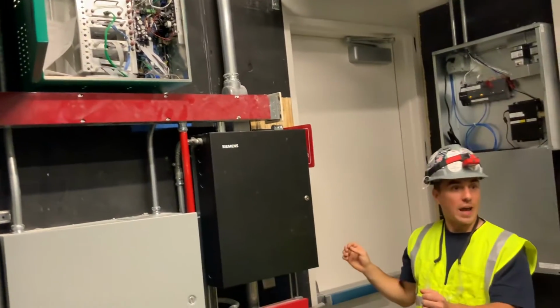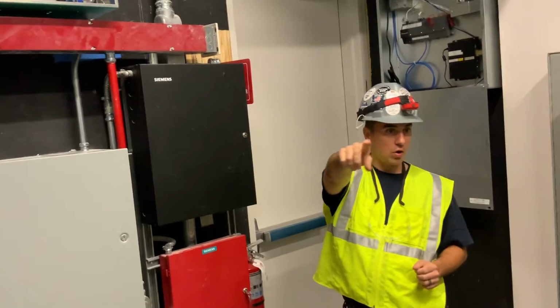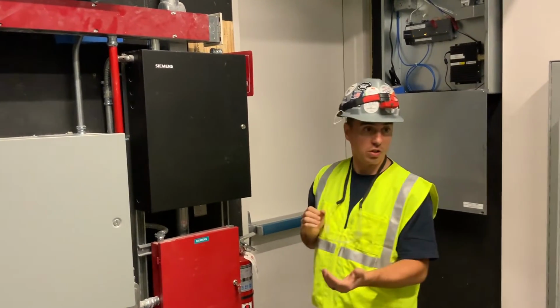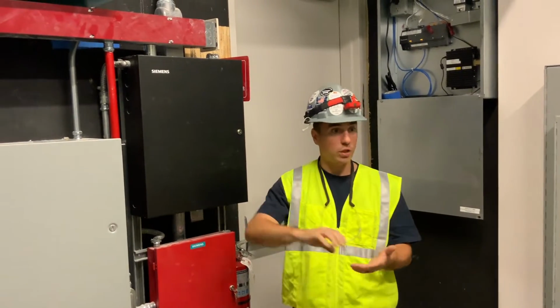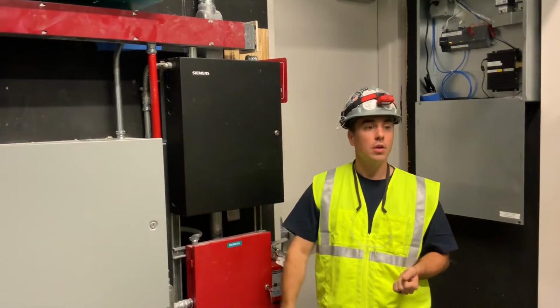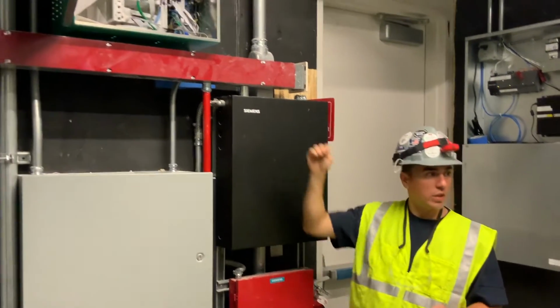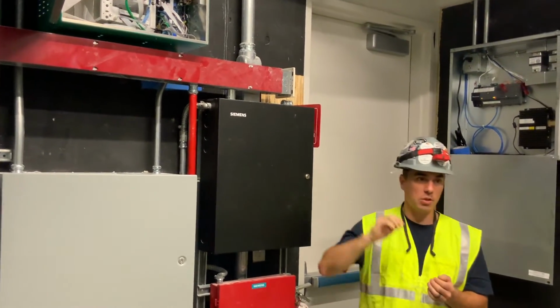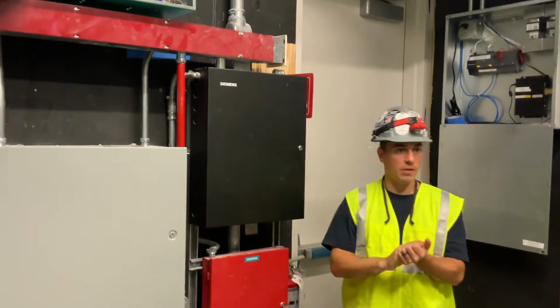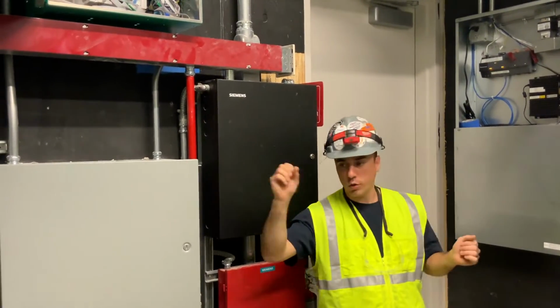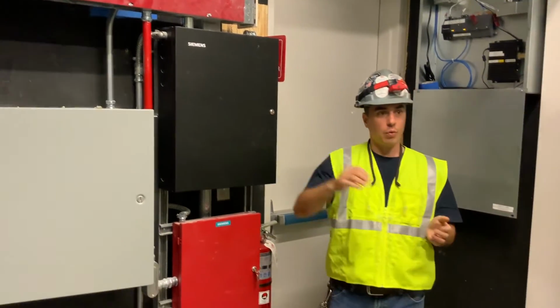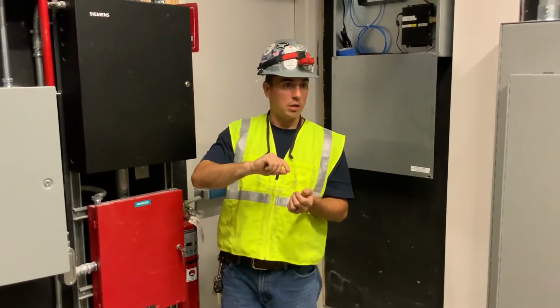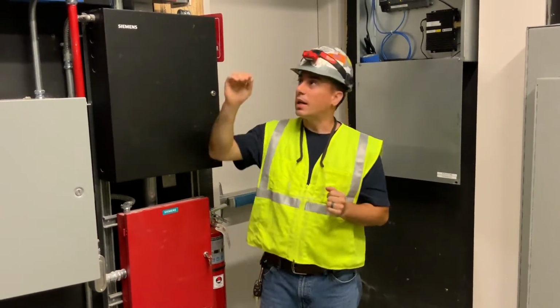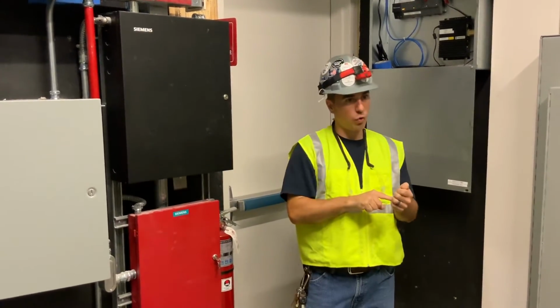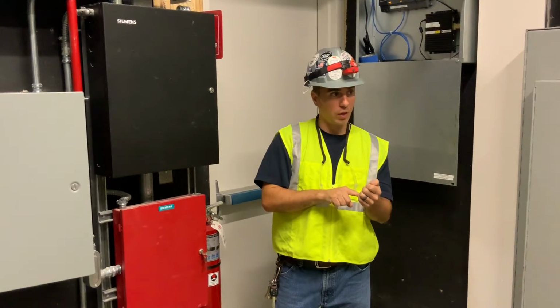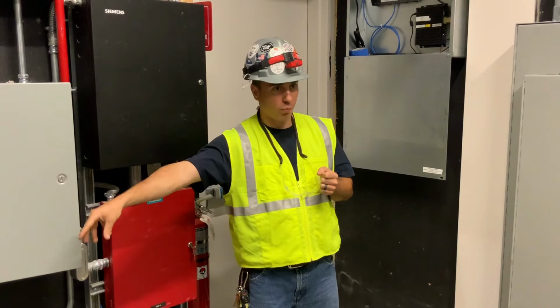There's a series of air data routers going down the main hallway here. And those routers basically just have a series of solenoids in them. 4 solenoids for 4 test areas on each air data router. As you hear this, the noise kind of changing. What it's doing is the AIRCUITY system is going and it's saying, okay, room 1, I want to pull a packet of air. And so it opens up the series of solenoids to pull a packet of air from room 1. It will then run at a transport speed. So that's why you hear the volume changing. It's going to run at a transport speed to pull enough air through the green tubing, through that solenoid, to get air where it's just pulling from room 1 now.